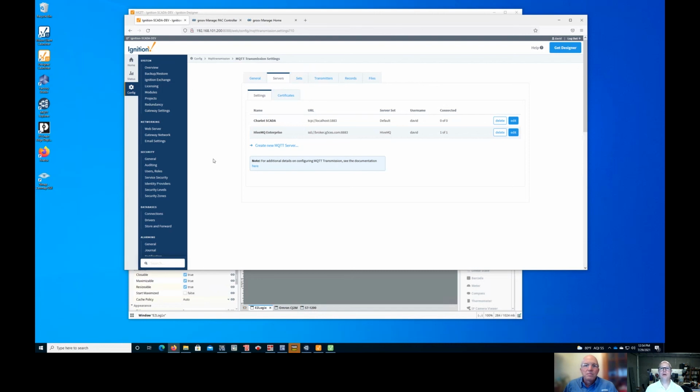So if you do have an area level, where I'm in this particular area and I'm line 1 and I'm line 2, now you can take advantage of Sparkplug. You'll have an area broker that then comes into your IoT platform, and then you can take that information, put it all together, and publish out that overall robust unified namespace that fits with an enterprise site. So this would become a site broker.